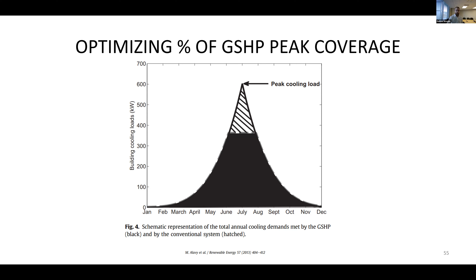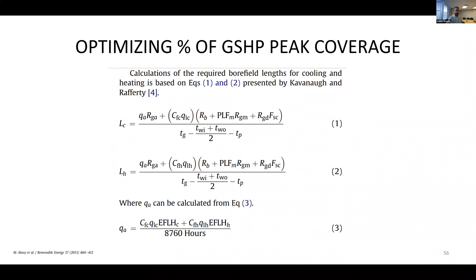But by using those formulas, you can develop these curves looking at your initial costs, which increase the larger the system gets, and then the net present value, looking at both operation versus initial cost of the system. So what we want to do is find this low point, essentially. Come down here, and this is going to give us our alpha, essentially, which influences this formula.